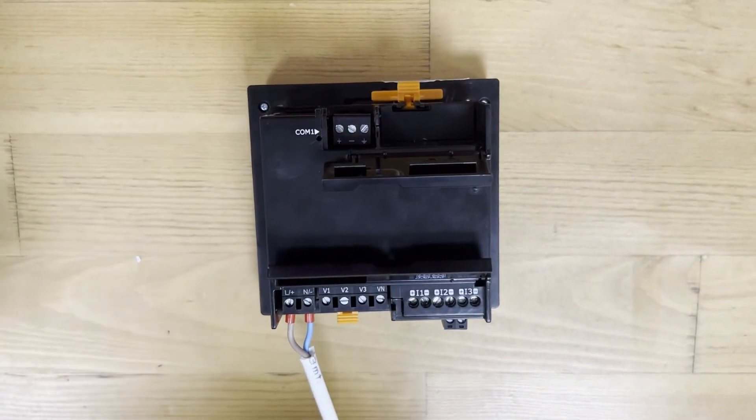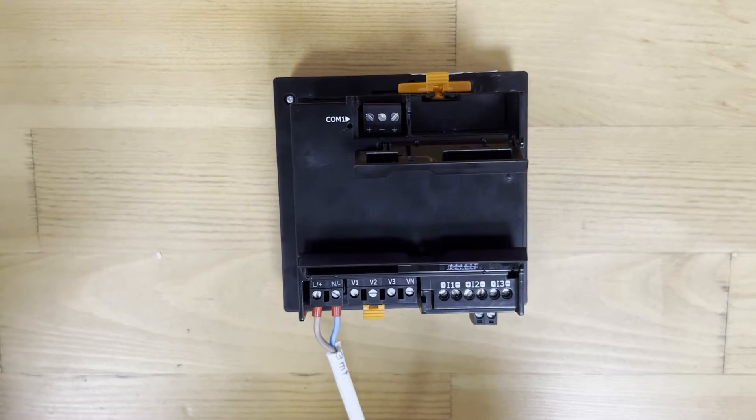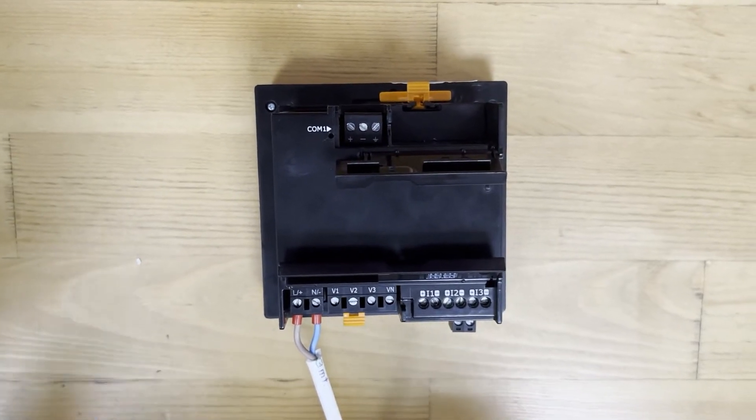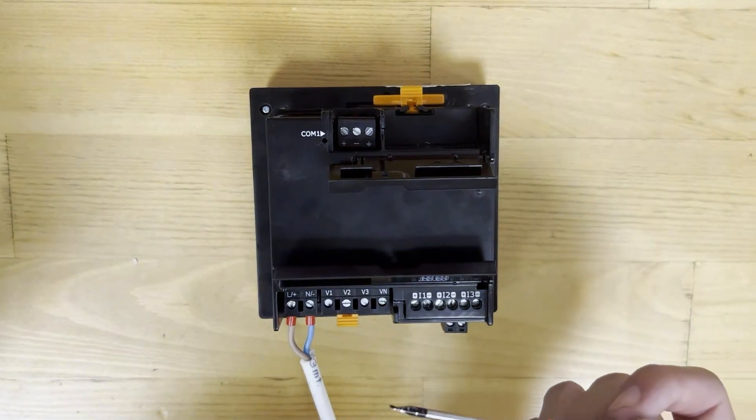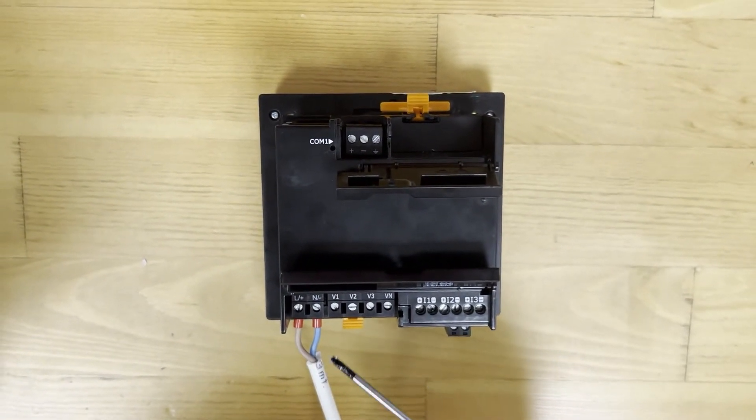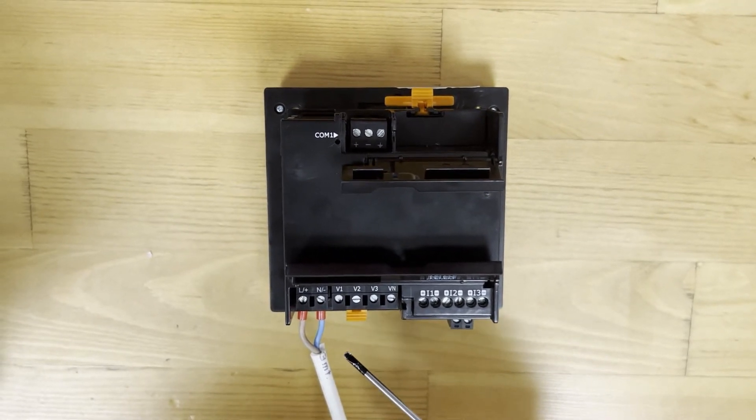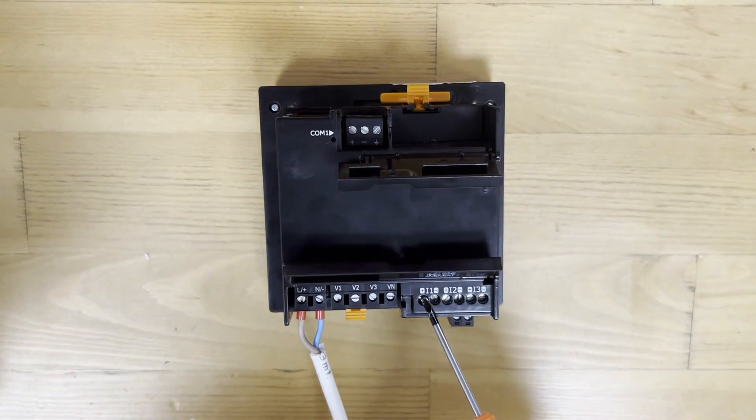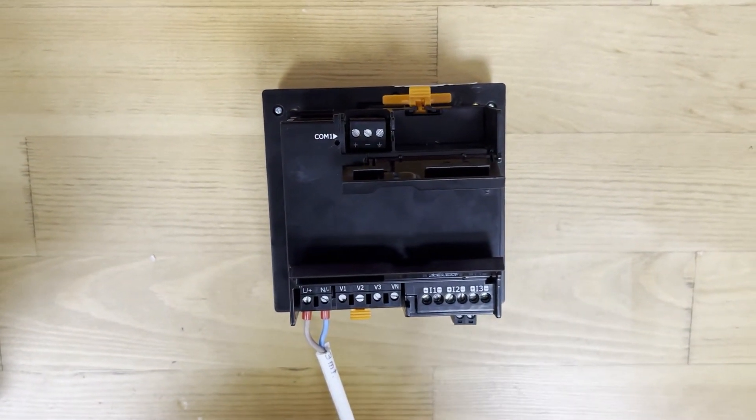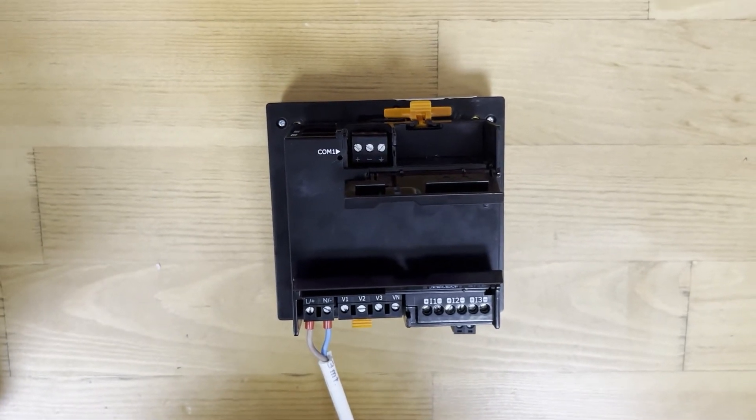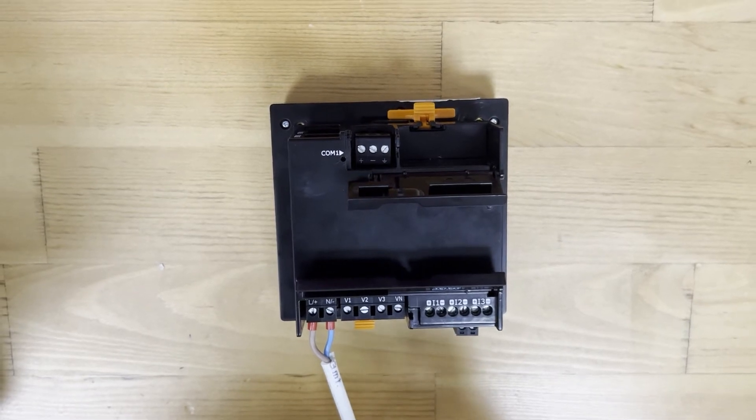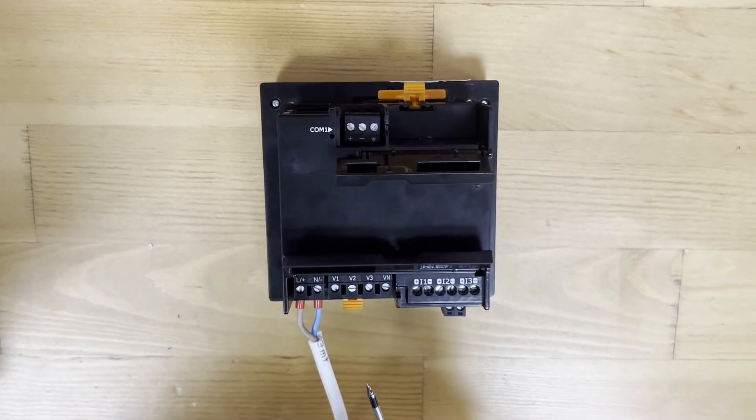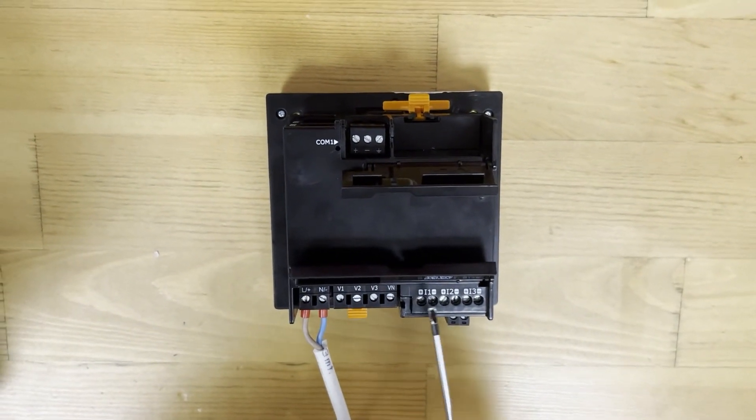Pro allows the measurement of 1 to 4 independent DC sources via 3 independent DC voltage inputs. When the Pro is used as a single DC meter, V1 and I1 must be used. V2 and V3 must be connected to ground. When used as a multi-channel DC meter, V1, I1, V2, I2, etc. are used as independent channels.